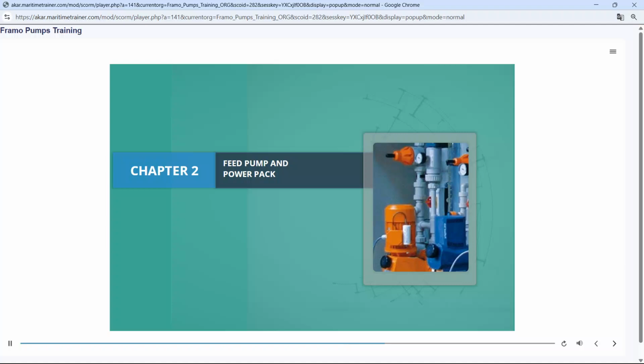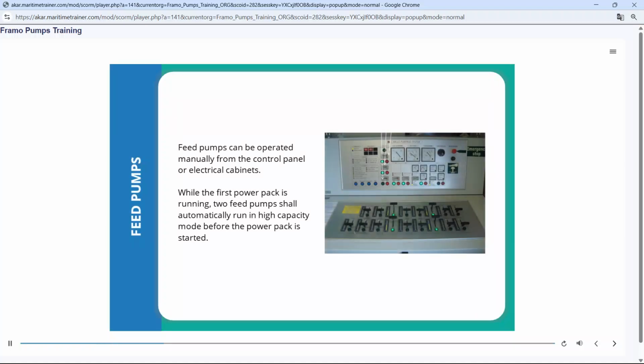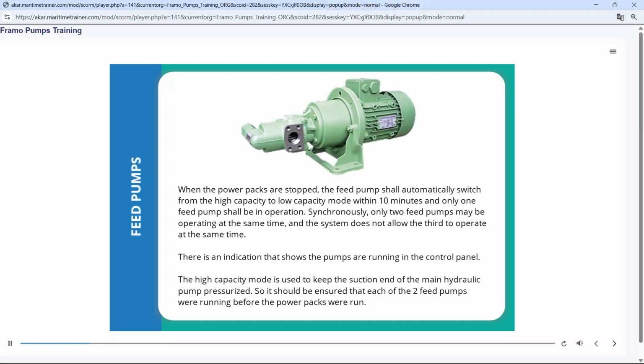Chapter 2. Feed Pump and Power Pack. Feed pumps. Feed pumps can be operated manually from the control panel or electrical cabinets. While the first power pack is running, 2 feed pumps shall automatically run in high capacity mode before the power pack is started. When the power packs are stopped, the feed pump shall automatically switch from high capacity to low capacity mode within 10 minutes, and only 1 feed pump shall be in operation. Simultaneously, only 2 feed pumps may be operating at the same time, and the system does not allow a third to operate at the same time.